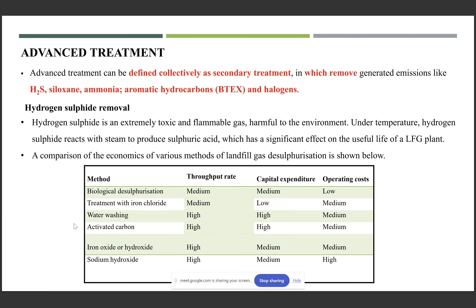For other landfill gas contaminants like ammonia, aromatic hydrocarbons, and halogens, these are generally at a lower concentration. If the concentration of ammonia is below 0.1 milligram per meter cube, aromatic hydrocarbons below 1 milligram per meter cube, and halogens below 0.1 milligram per meter cube, then there is no need for treatment. So this gas can be used without any additional treatment. Only primary treatment will be required.